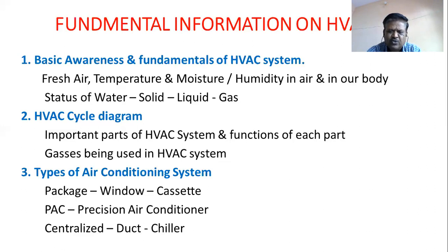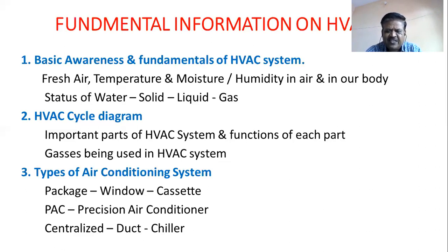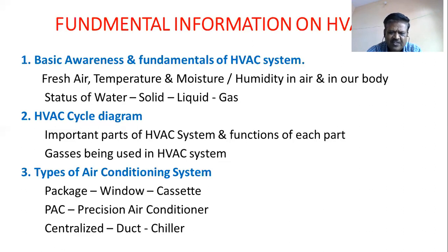The temperature should be within 22 to 25 degrees centigrade. The moisture — technically that is humidity — should be controlled, within 40 to 60. And of course filtering the contaminations, the dust particles, that is particulate matters in the air. That is how to create filtering, how to supply human comfort, how to circulate this type of air.